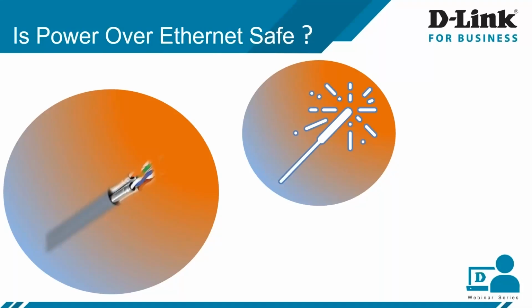To avoid such a scenario, it is really important that we follow the NEC. The NEC has already defined how many cables should be in the bundle, with what conductor size and what temperature. So always follow the TSB-184-A guideline for installation, the NEC guideline, and the certification method. If you had certified or tested this cable, you could have caught that it is CCA and not copper cable. This helps in avoiding the worst case scenario, which can cause an accident.